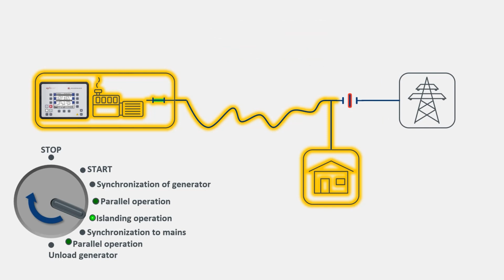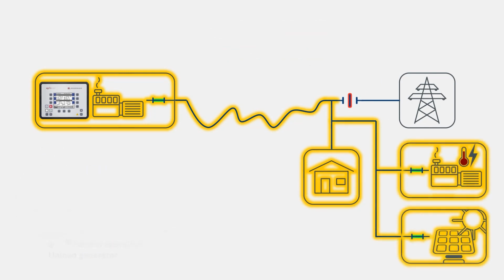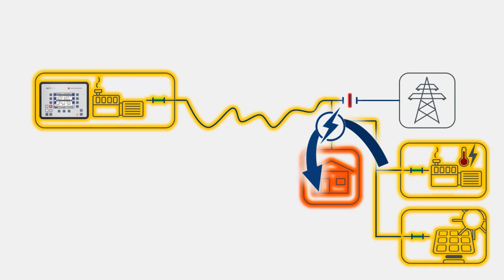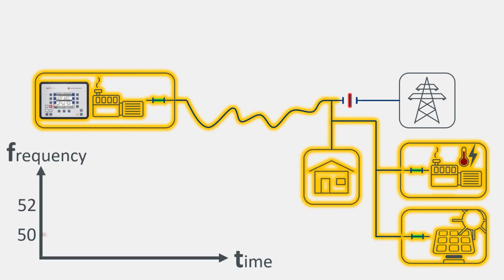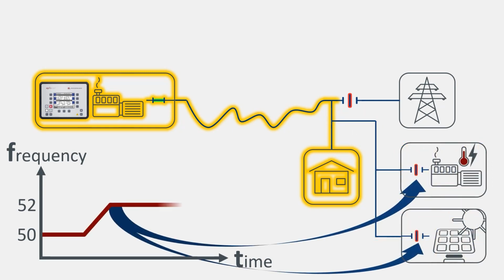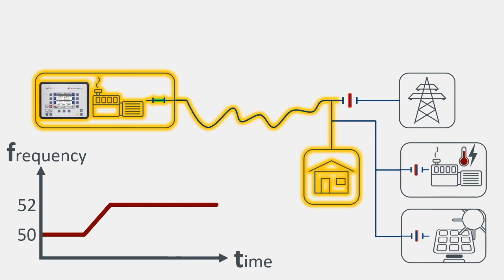We want to avoid reverse power from grid-tied photovoltaic or other cogeneration power plants, as these can damage valuable assets. To ensure distributed energy resources get disconnected and stay disconnected from the utility, it is necessary to increase the frequency to 52 Hz. This will force those grid-tied renewable resources to disconnect, and thus valuable assets are protected.